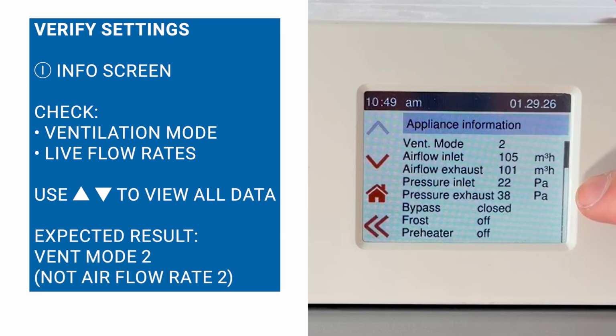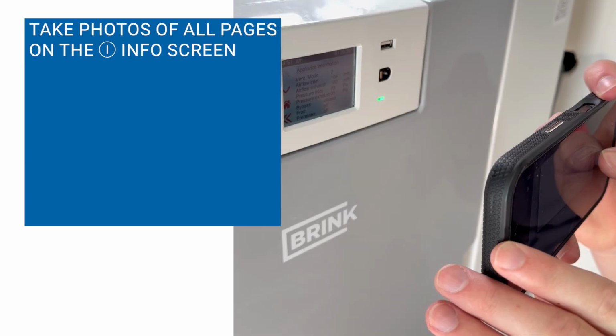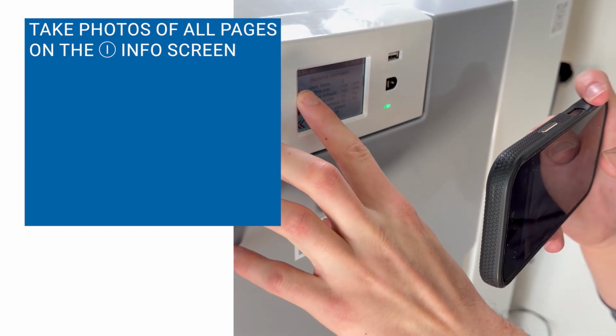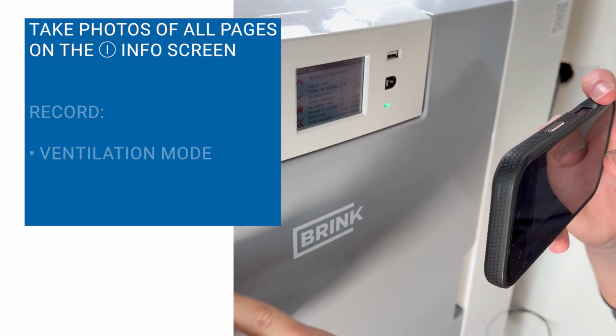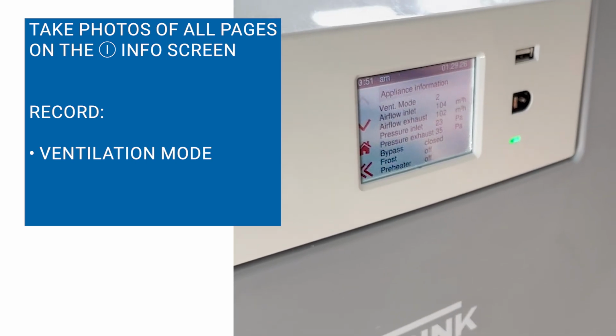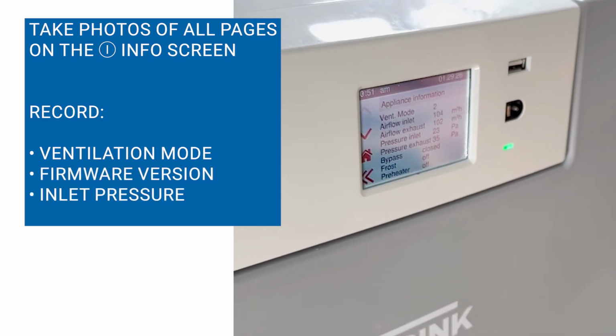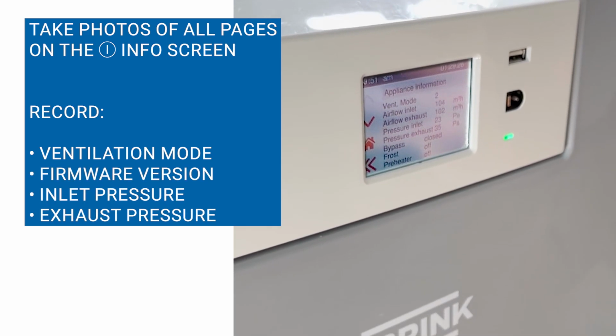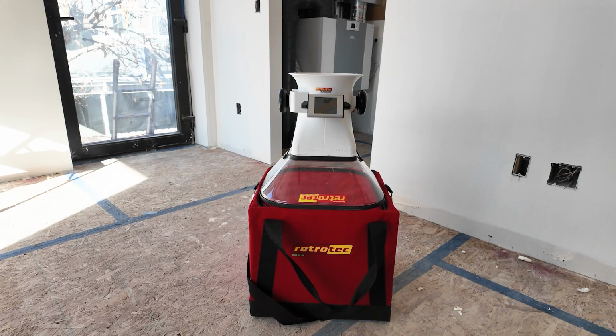This is not airflow 2. The measured on-screen flow rates should be at or very near your design. The commissioning agent should take a photo of all pages on the info screen and record the ventilation mode, firmware version, and the inlet and exhaust pressures. Let's get the flow hood set up and check that it's in the right mode.